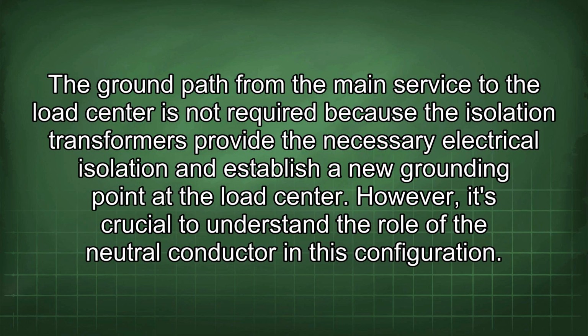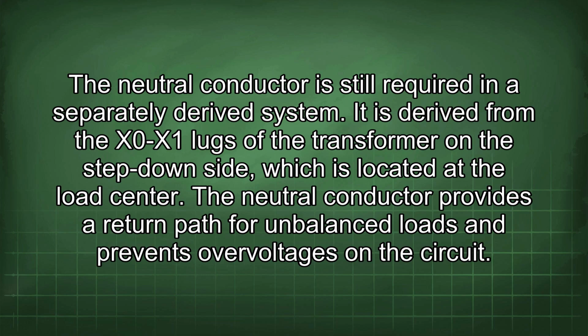The ground path from the main service to the load center is not required because the isolation transformers provide the necessary electrical isolation and establish a new grounding point at the load center. However, it's crucial to understand the role of the neutral conductor in this configuration. The neutral conductor is still required in a separately derived system.